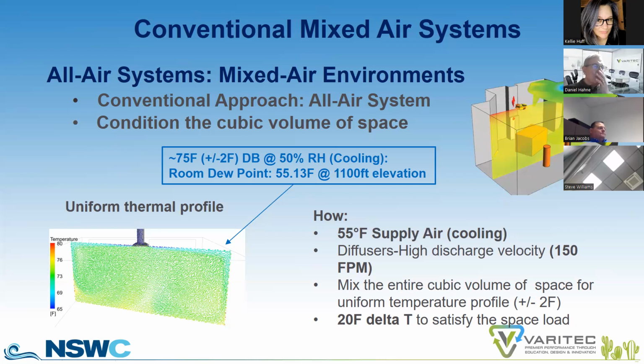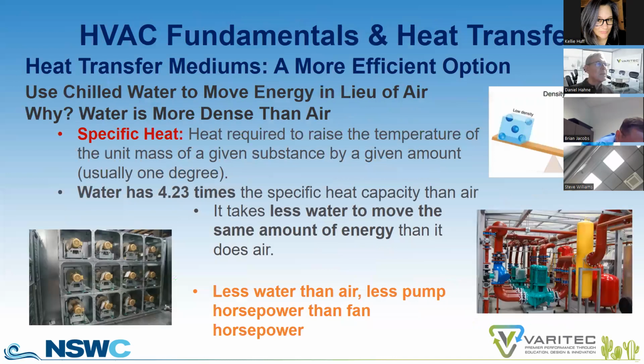Dan Inhout, previously VP of Engineering for Kruger, was adamant that a mixed air system is doing what it needs to be doing if it can maintain plus or minus 2 degrees temperature differential throughout the cubic volume of interior space. So is there a more efficient heat transfer option? What if we used chilled water to move energy in lieu of air? What if we applied the dense heat transfer medium characteristics of water? And what does that mean in an HVAC system? Why would we do that?